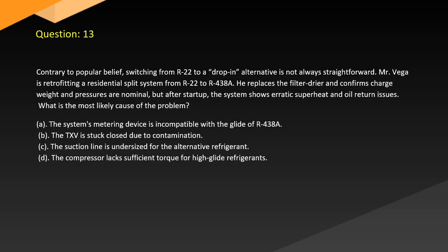Question 13. Contrary to popular belief, switching from R22 to a drop-in alternative is not always straightforward. Mr. Vega is retrofitting a residential split system from R22 to R438A. He replaces the filter dryer and confirms charge weight and pressures are nominal, but after startup, the system shows erratic superheat and oil return issues. What is the most likely cause of the problem?